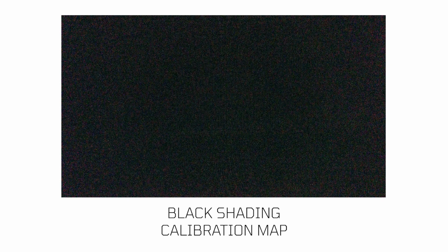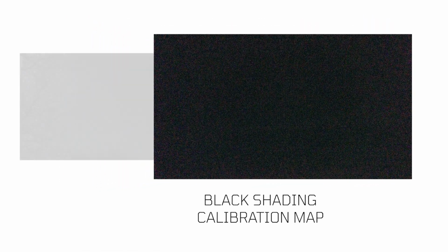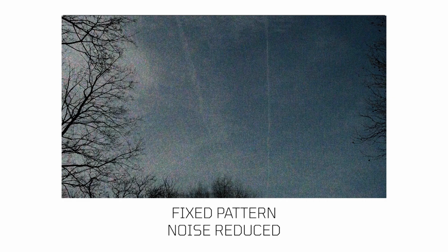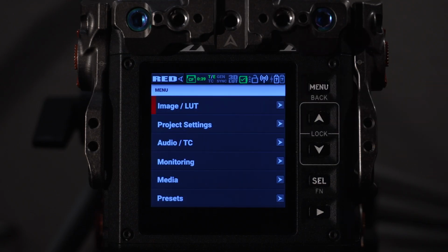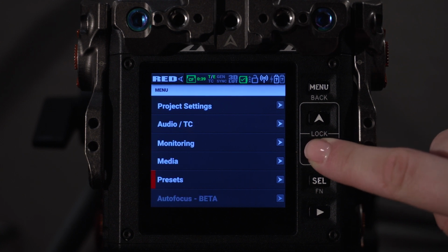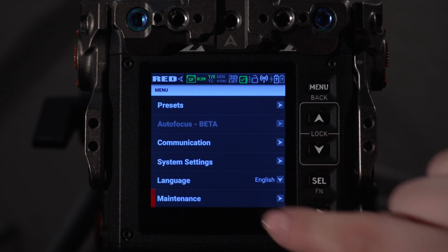It ensures that the pixel sensitivity remains consistent and clean throughout the image. Black shading measures the pattern of fixed noise, saves it, and then subtracts the fixed noise, so only the random noise is left behind. To perform the calibration, press Menu, Maintenance, Calibrate, and then press OK.